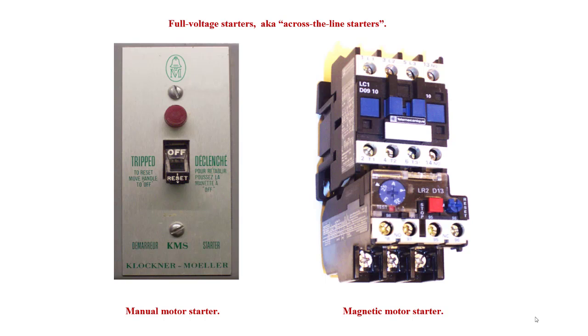But when we get into really large horsepower motors and hard to start motors, these motors can have a huge inrush current. So if I had say a 500 horsepower motor, 600 volt, and it's roughly 500 amps while it's running, we could see anywhere from 5 to 6 times the inrush current on that. So that can cause a lot of problems. We can have all the lights go dim, brownout situations, extremely hard on the utility. So often we're going to be required to put in some sort of reduced voltage starting. And that's what this module is about. How are we going to get these motors starting and limit the inrush current to get them going?